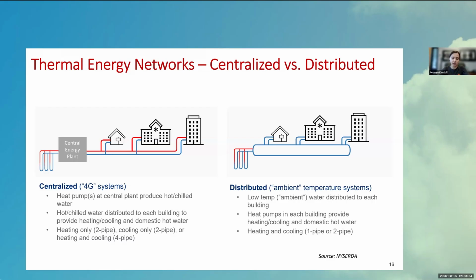And then versus the centralized system, you can have a decentralized or distributed loop, which is kind of more what we saw on the previous diagram, where you have low temperature ambient water distributed to each building, and the heat pumps in each building, instead of in a central location, provide the heating, cooling, and hot water. This can be a one-pipe or two-pipe system.